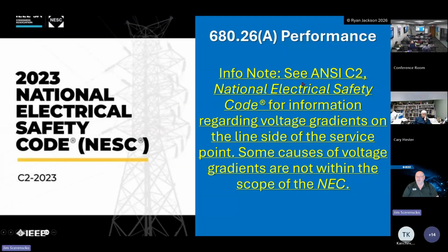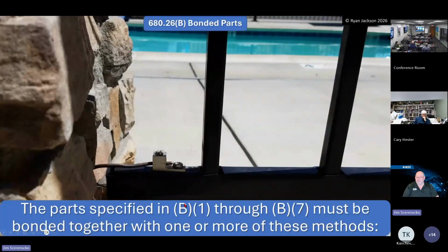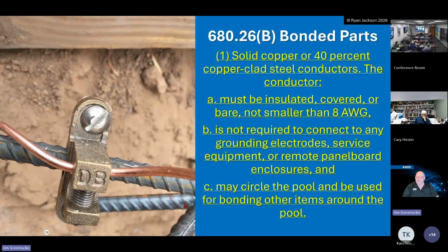680.26(A), the informational note for the ANSI C2 National Electrical Safety Code, which is what the power companies use. Regarding voltage gradients on the line side of the service point, some causes of voltage gradients are not within the scope of the NEC. We have had a lot of problems where you have voltage leakage through the ground from the utility, and it causes problems on the pool. You know, specific parts are required to be bonded. Any metal part within 5 feet of the pool.